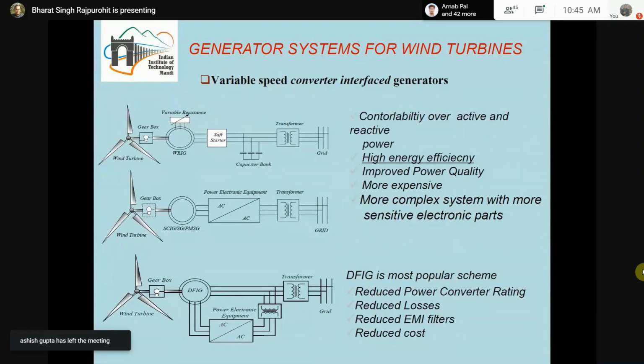Fine. Okay. So how is this DFIG induction generator operating? The concept is very basic. You can compare from the topmost figure: when the power is extracted from the rotor by having a variable resistance, in this case a power electronic converter is there, which is also able to extract power. And this power, instead of being wasted in a variable resistance, can be converted back to suitable AC of specified voltage and frequency and sent to the grid. So the power that was earlier wasted in the resistance can be utilized. This is how some efficiency improvement is also there.